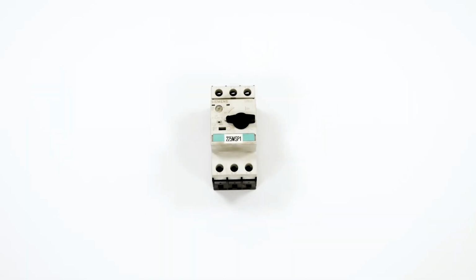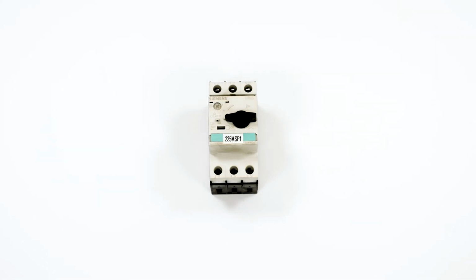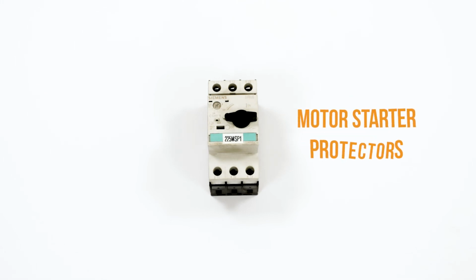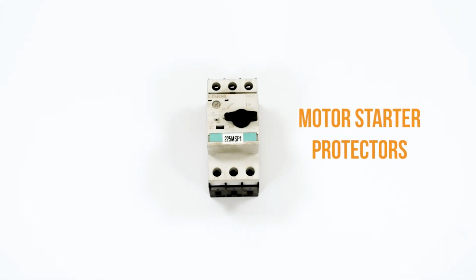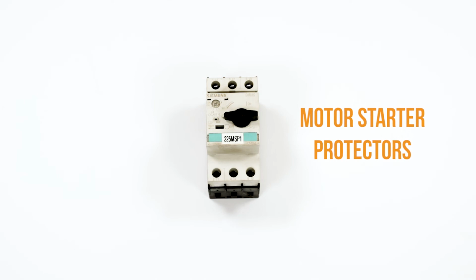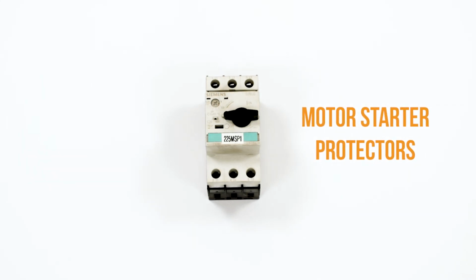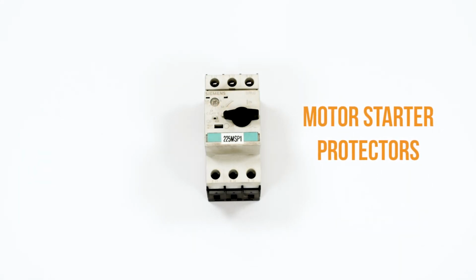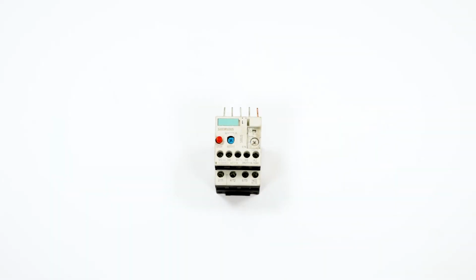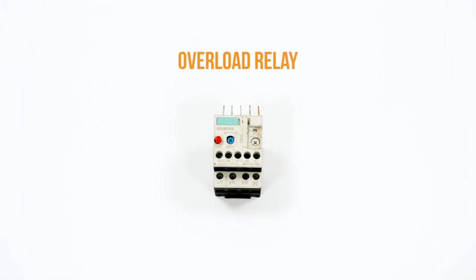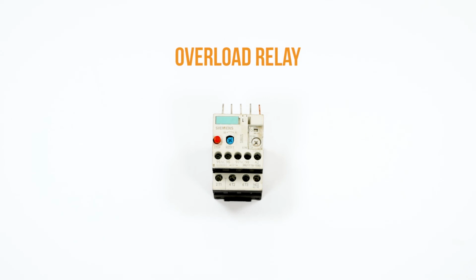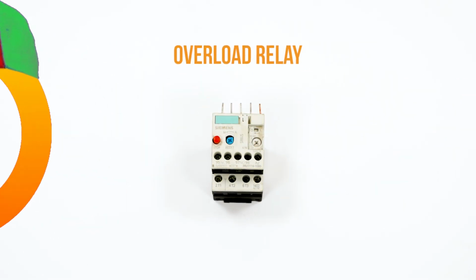Our next two types of overcurrent protection devices are both thermal overload devices. Our first type are MSPs, or what we call motor starter protectors. These are like breakers, except they have a thermal overload release that prevents the circuit from closing until it returns to an acceptable temperature. A lot of them also have adjustable trip settings. Our final overcurrent protection device and our second thermal overload device is an overload relay. These are used after a contactor, and they have thermal overload releases, just like our MSPs.